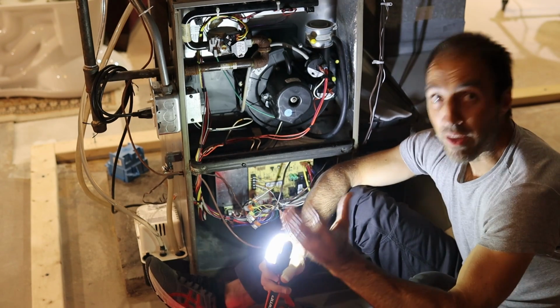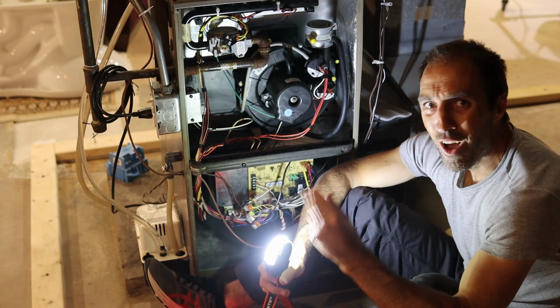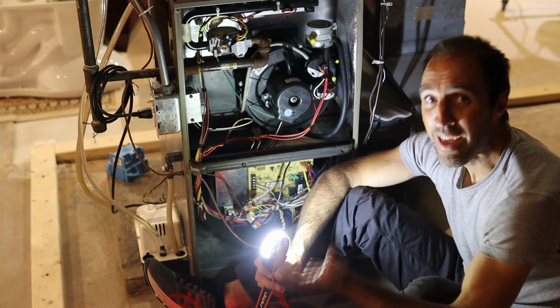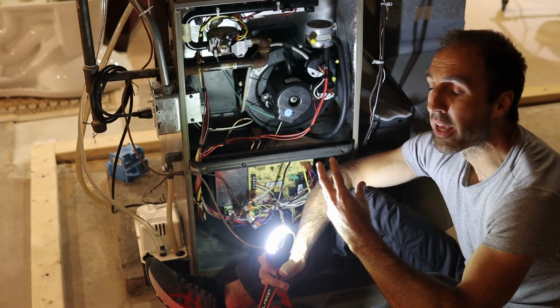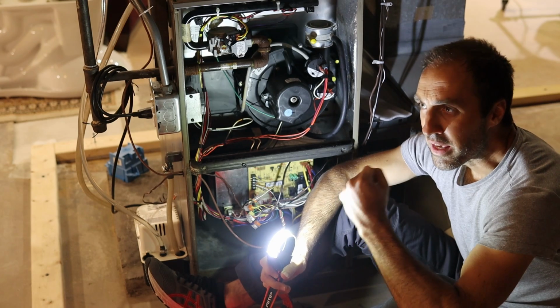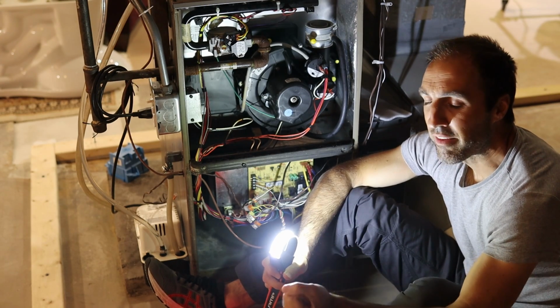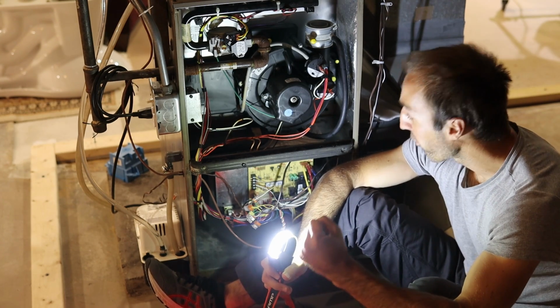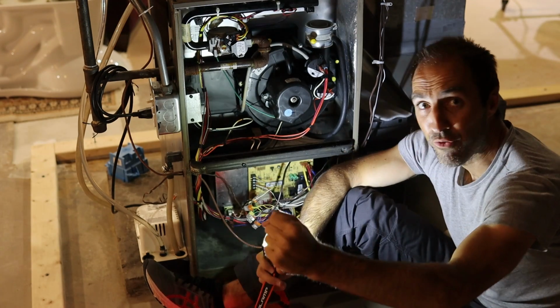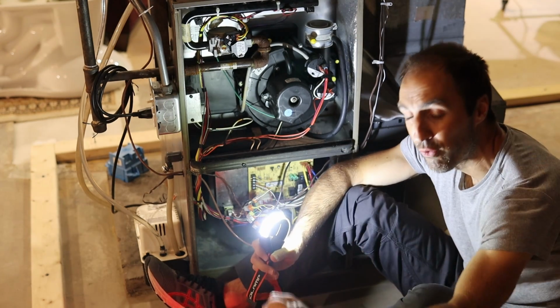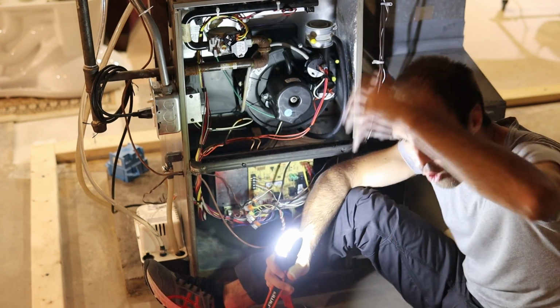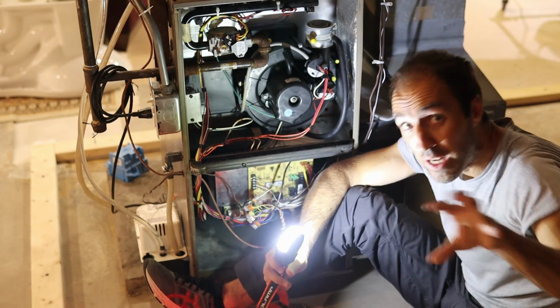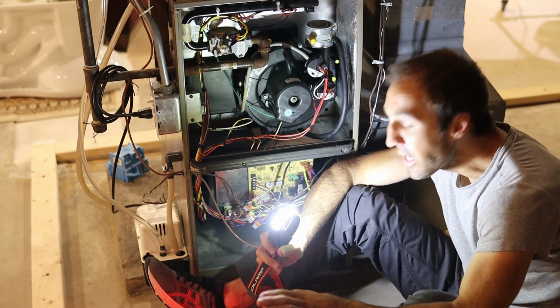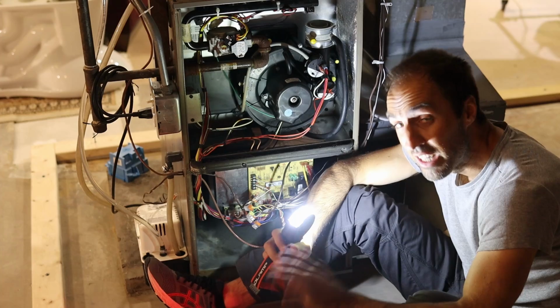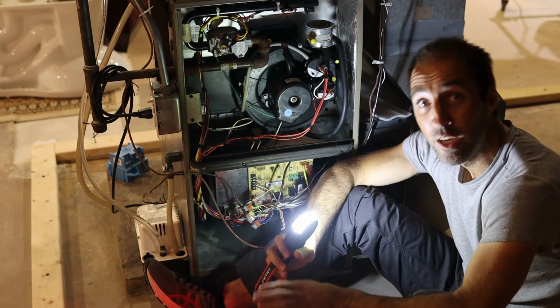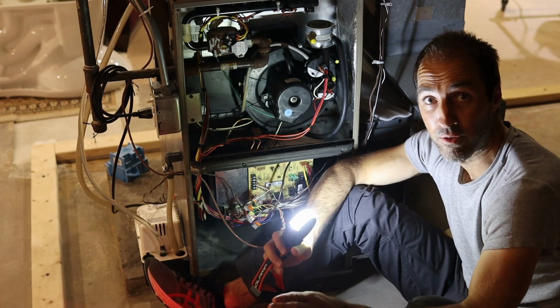The warmness in the air, or the warm units, are delivered by the CFMs. Think of it like kids getting to school on the school bus. The school bus is the CFM. It is the airstream, it's the airflow. Heat, which is the kids, ride on the airflow to each of the rooms. You need the CFM to deliver the heating or the cooling to any room in your house.